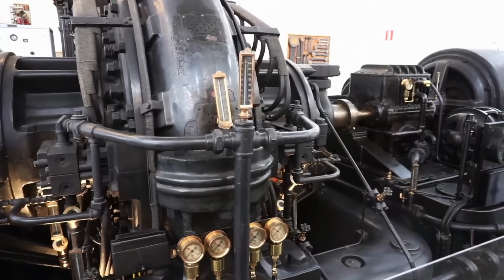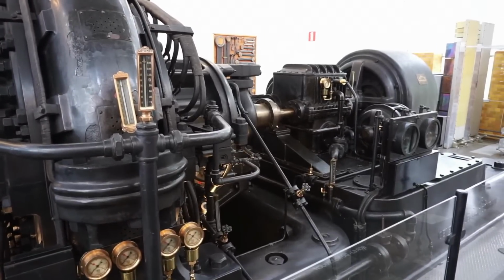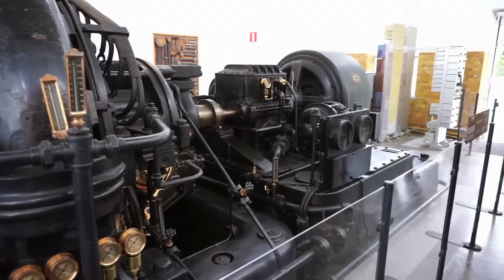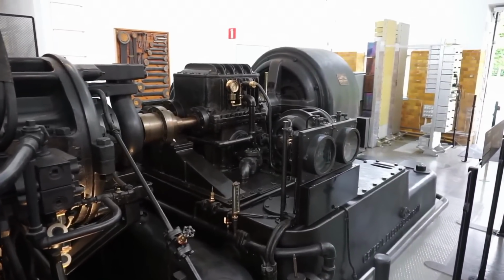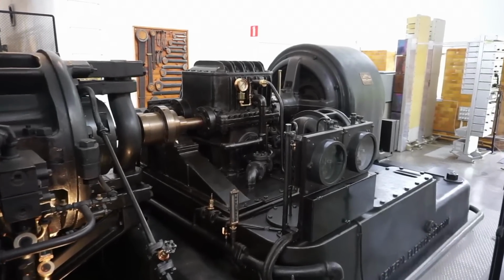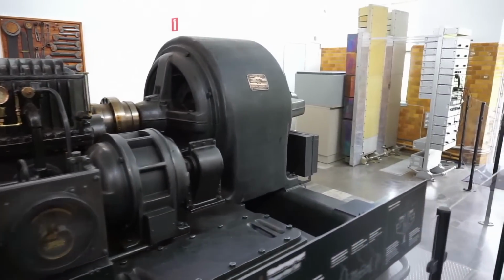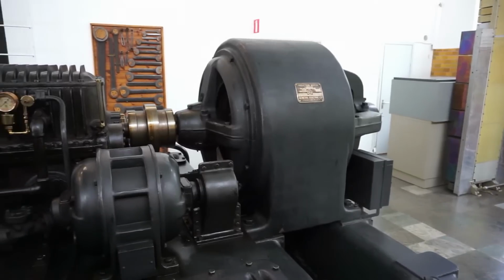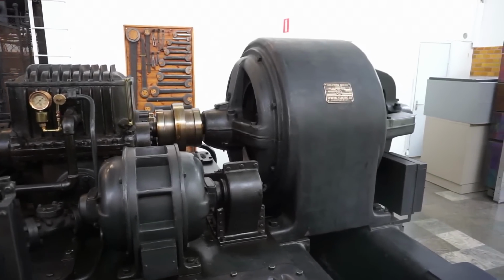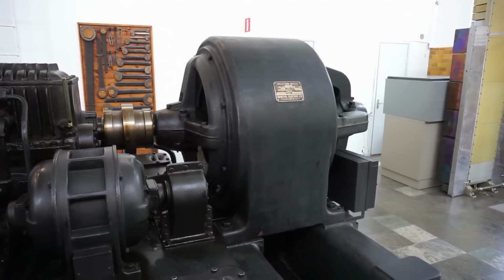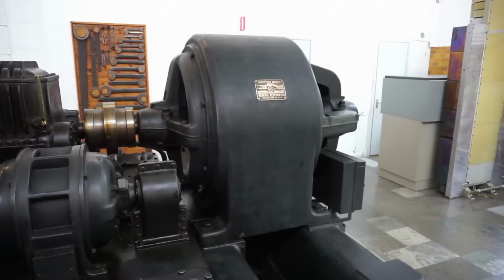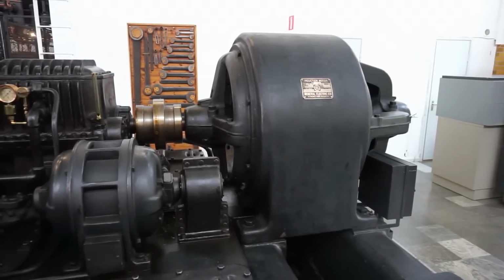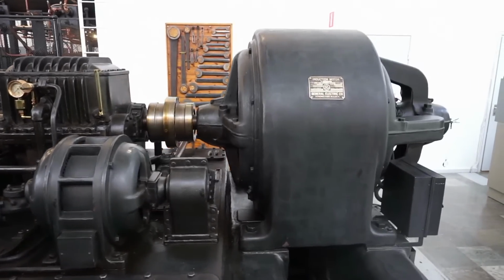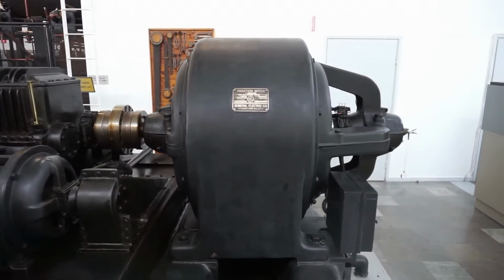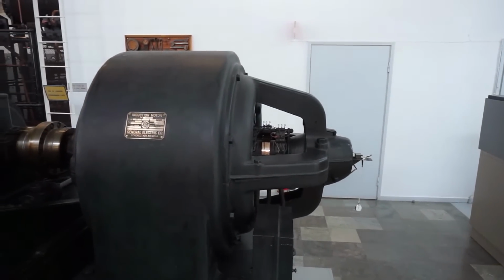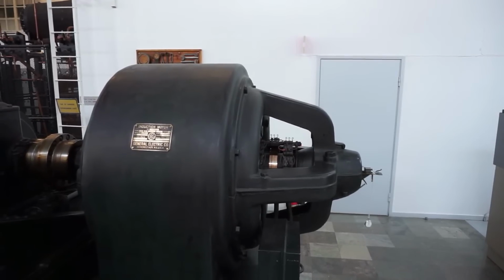The disk is driven by the main motor via the gearbox. So the speed of the motor is directly related to the speed of the disk or the frequency on the alternator. The main motor is a 500 horsepower asynchronous motor driven by 2.3 kilovolts two-phase voltage. The stator is two-winded and the rotor is three-phase winded. We can control the speed of the motor in two ways. By transductors in line with the stator winding, we can control the voltage. I will show the transductors later on. Via the rotor, it's the second way. The three phases are connected to liquid resistors via slip rings. You can see on the motor shaft there.